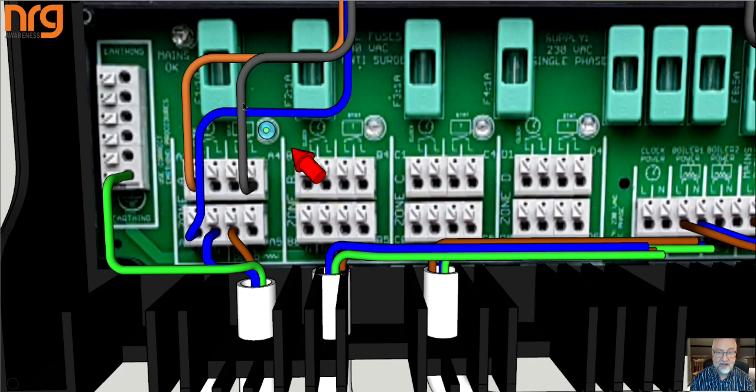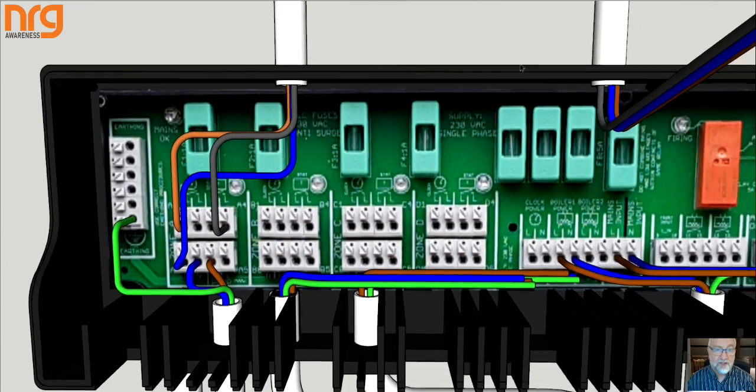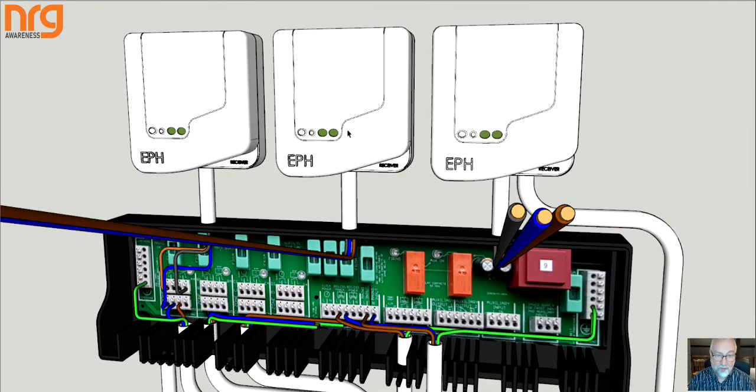In this scenario, it tells you that the OpenTherm system has sent its live down calling for heat, and you know that that particular controller for the OpenTherm is working properly. So same applies with the OpenTherm LEDs. They have a power light to tell you that they're actually energized, which you can see that the board has energy. But if that light is not lighting, you know for a fact that the fuse is gone in the zone. So all the fault finding is built in to the complete system. Without tools, you can see straight off what is working, what isn't working, what should be working.